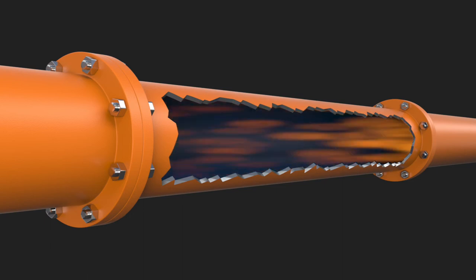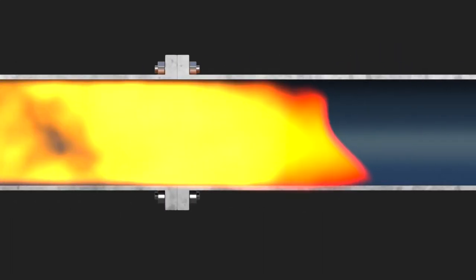It follows therefore that the use of a stable detonation arrestor in isolation is not suitable, as it would not stop a detonation in the DDT phase.